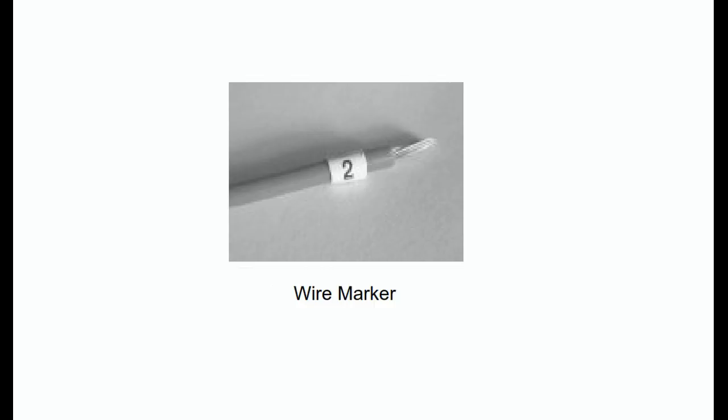The wire generally used within the controls circuitry is AWG14 or AWG16 stranded copper, type MTW or THHN.